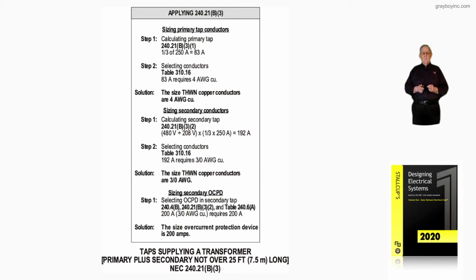Now, step two, Table 310.16. The 83 amp tap on the primary would have to be number 4 conductors, because we're in the 75-degree column. We're permitted to use that because those were the terminal ratings of the equipment. So we pick up a number 4, good for 85 amps. So the solution for the primary tap, the answer is number 4 THWN copper conductors.